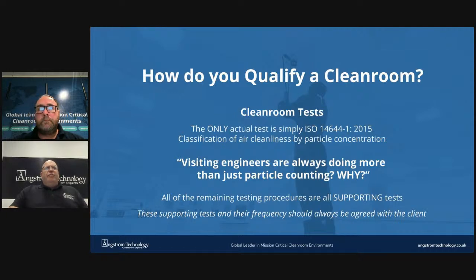All of the remaining tests covered in ISO 14644 Part 3 of 2019 are supporting tests only, which are appropriate for measuring the performance of a clean room. And these supporting tests and their frequency should be agreed with the client beforehand. Dependent on the design specification and URS created by the client, this will determine which additional supporting tests are required when requalifying the facility. Temperature and humidity ranges, room differential pressures, lux levels are examples of these, and the pass-fail criteria will be determined by the specifications in the URS.